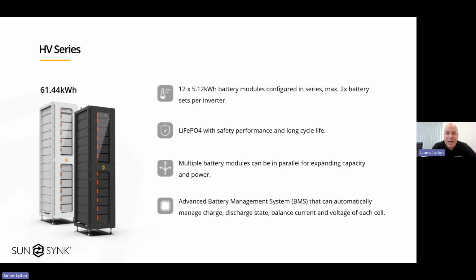You can connect up to 16 high voltage battery stacks to a 50 kilowatt inverter, let's say. This gives you an idea of the scale of the systems you can create, and that's 16 racks per 50 kilowatt inverter, and you can parallel 10 50 kilowatt inverters together. So yeah, quite endless.